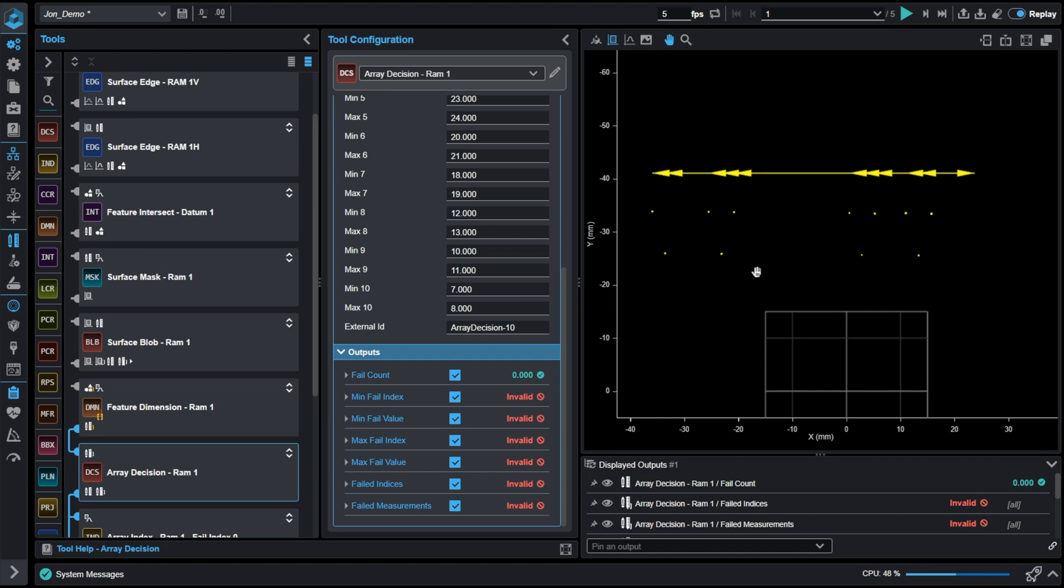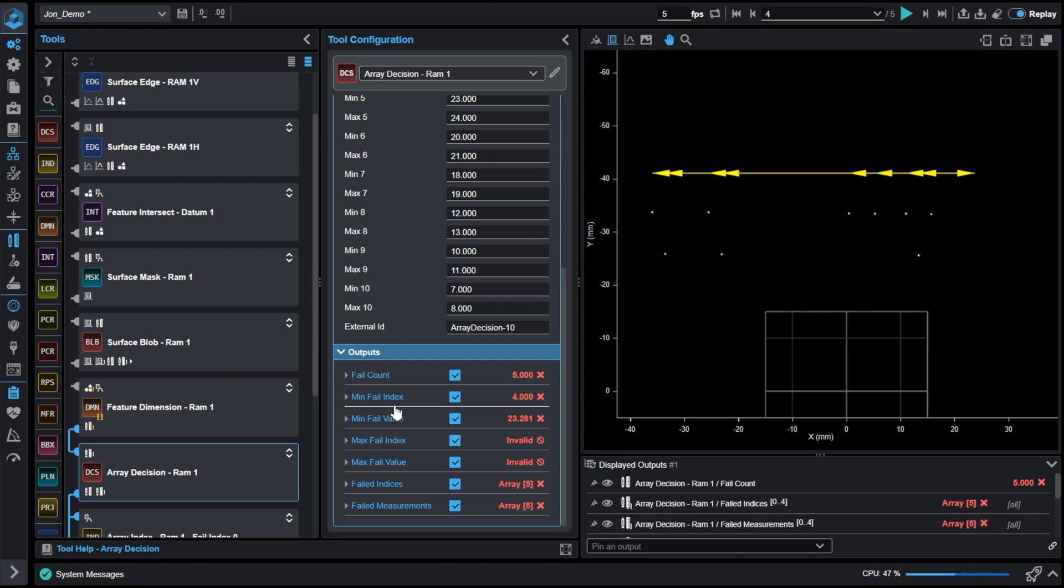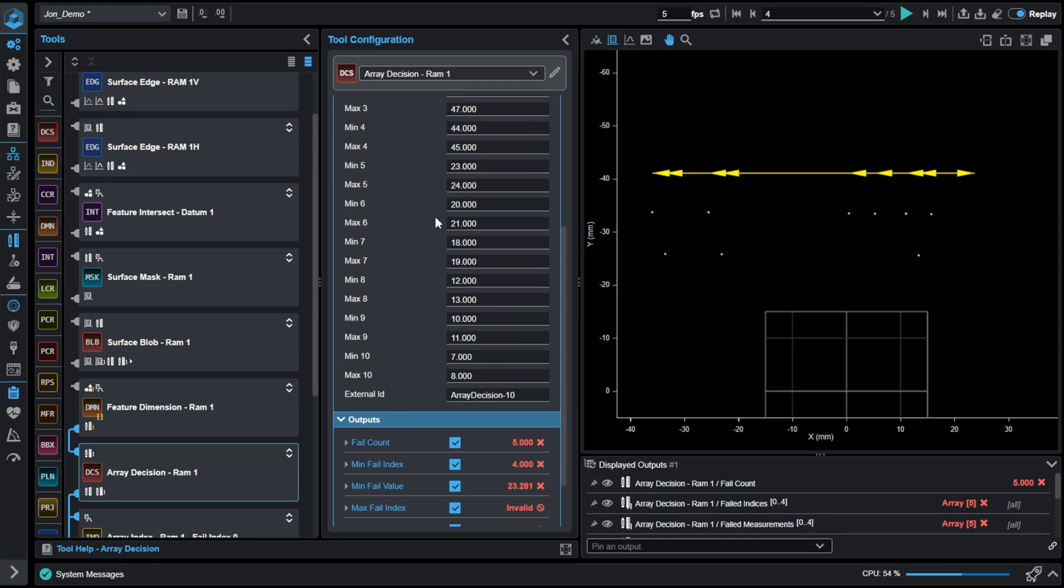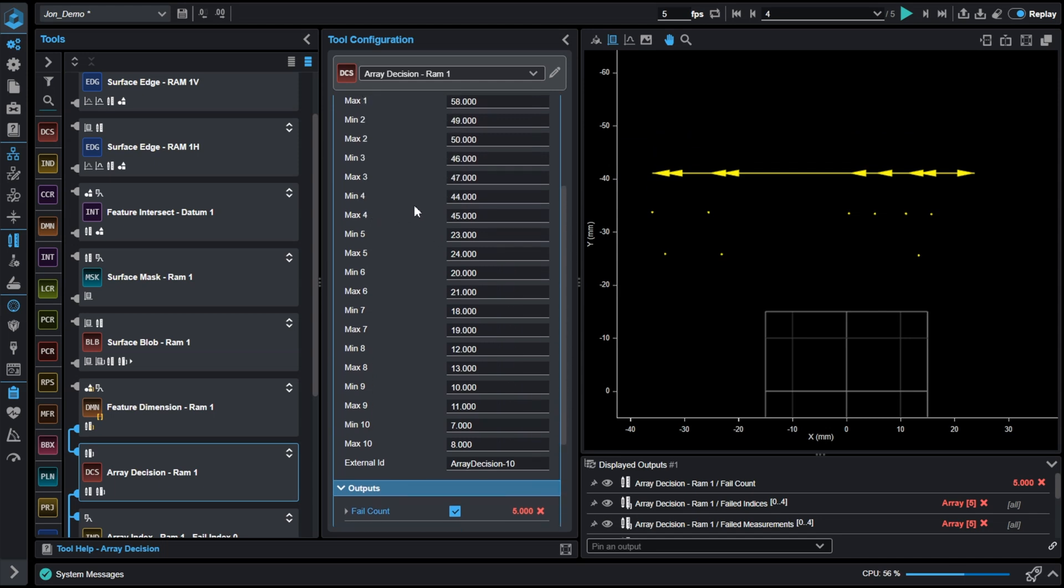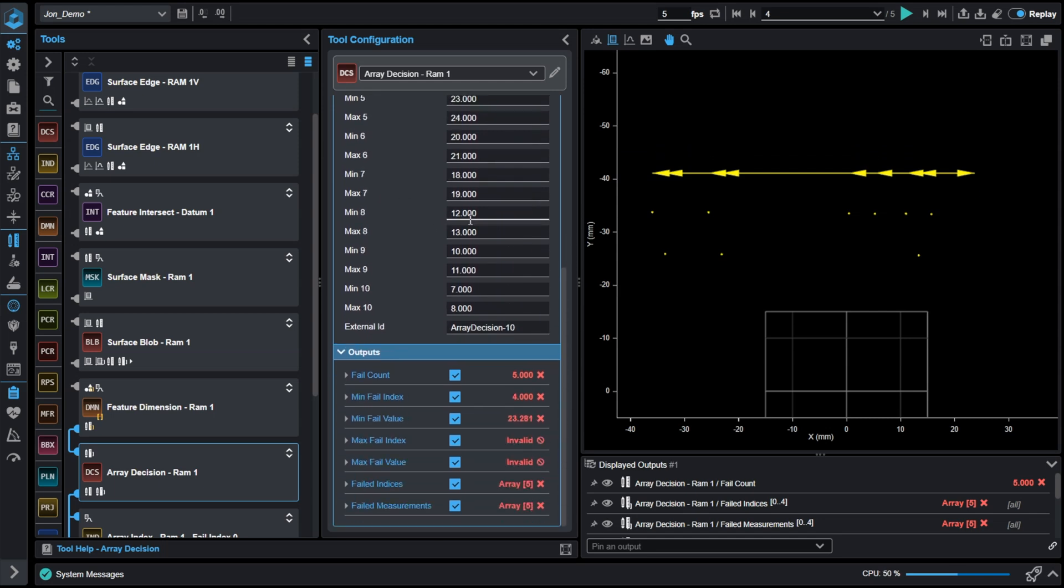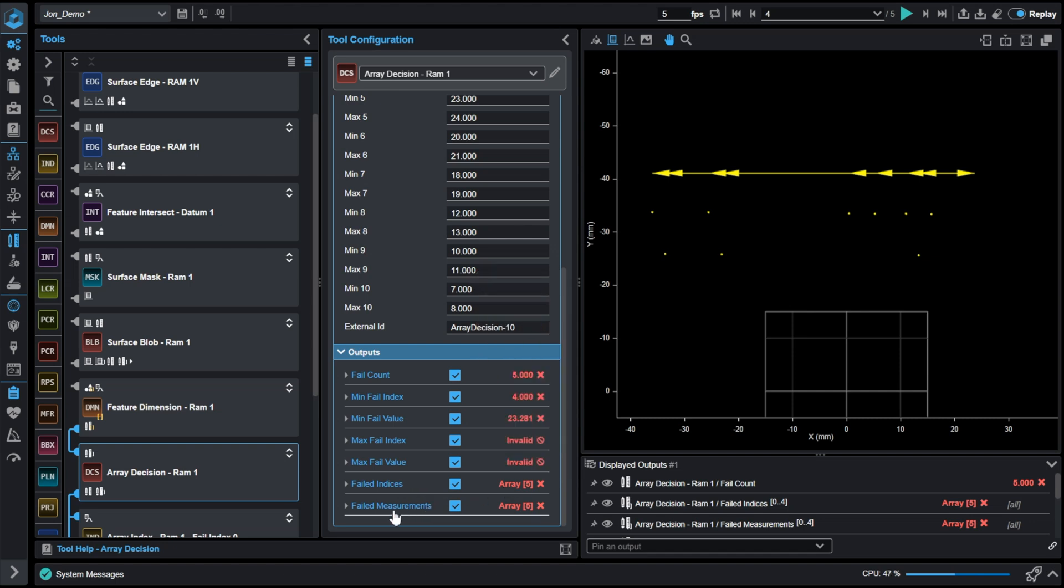But if we go to an example where we are missing a microchip on scan four, we can see now we have a fail count of five elements are now failing, with our minimum fail index being element four with a minimum fail value of 23. If we go to four, we're outside of the range that we've set here. The valuable part of this is the array that we can output here in failed indices. We have an array element four, five, six, seven, and eight failed.